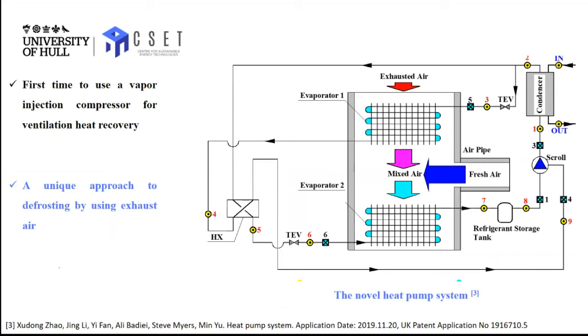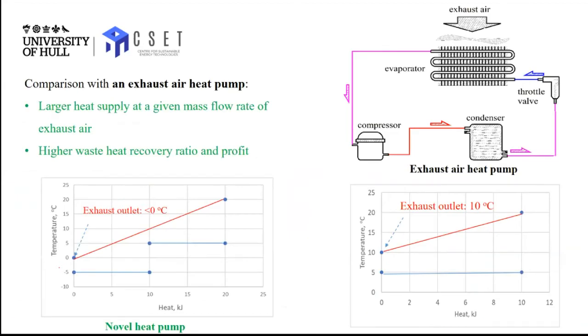So look at this technology. We can say we make the first effort to use a vapor injection compressor to recover heat from ventilation air. And we make use of ventilation air to defrost the heat pump rather than use electricity. Okay, compared to a traditional exhaust air heat pump, which has a single stage evaporator and relatively small heat recovery volume and capacity, our new heat pump, because we have a two-stage evaporator and we got vapor injection in practice in the heat pump, would be able to recover double the heat energy from ventilation air.